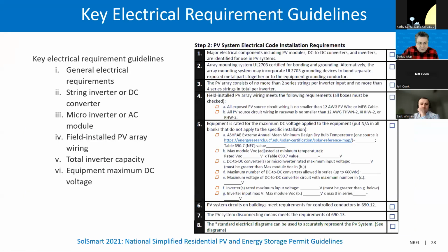So the second thing is the electrical review. In this section, we will cover the requirements related to each code. The key electrical requirement guidelines include general electrical requirements, including the string inverter or DC converter, microinverter or AC module, installed PV array, wiring, total inverter capacity, equipment, and maximum DC voltage. This is also an example of SolSmart's checklist. It's a very detailed checklist where you can fill in your input. So this is also a good guide for electrical code installation requirements.